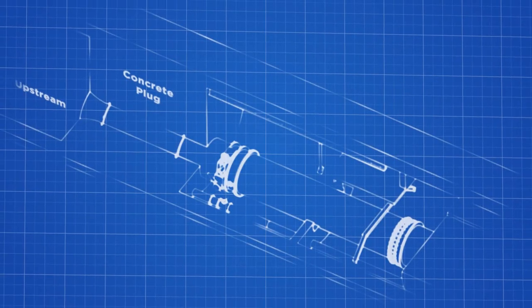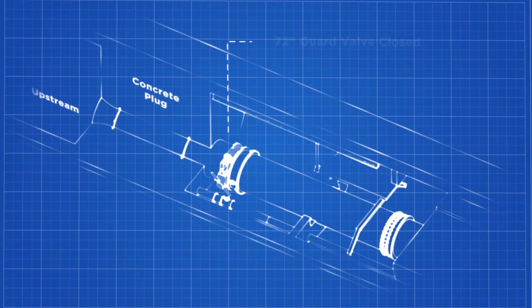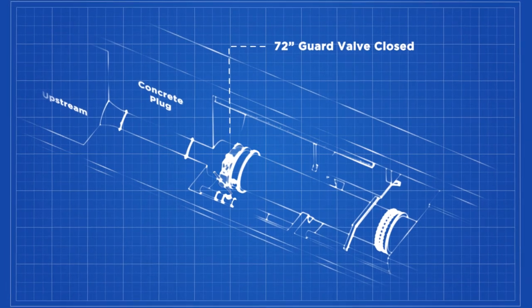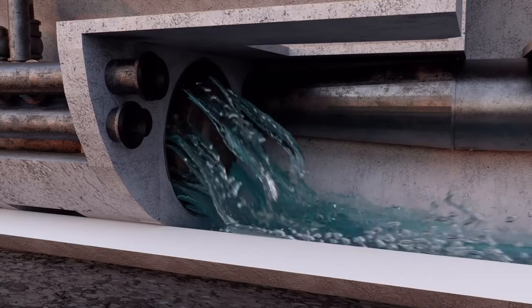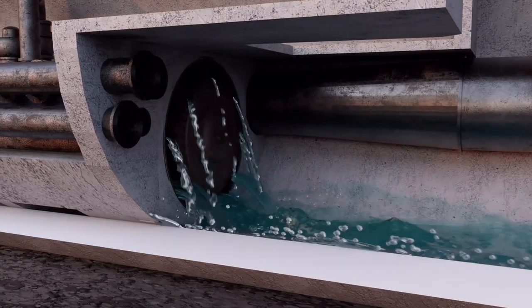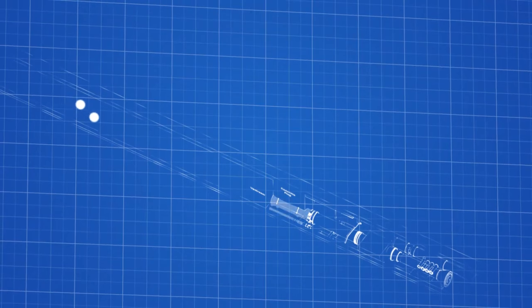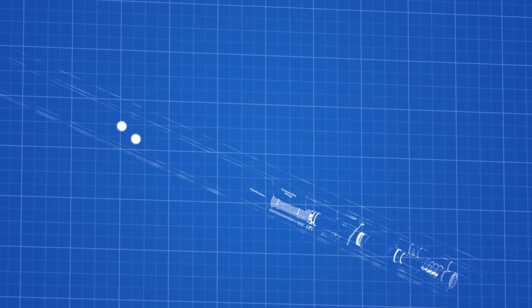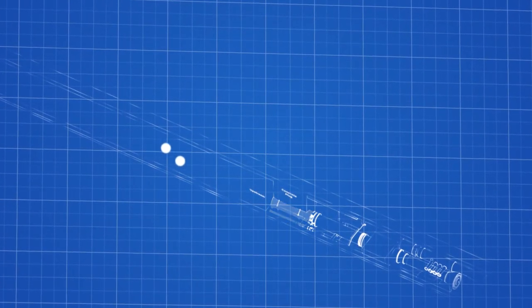At this point in the project, the large 72-inch guard valve was closed, reducing the flow through the low-level outlet to the minimum leakage rate past the valves. The Mohican entered the tunnel and traveled up to the upstream face of the concrete plug. Here, the Mohican used a different saw to trim the rebar protruding from the face of the concrete plug.